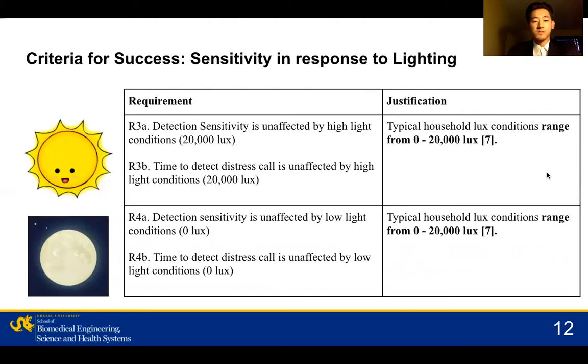The following requirements describe sensitivity performance in response to different light conditions. Lighting affects the functioning of not only the retina, but also constrictor and dilator muscles in the eye, which may affect EOG signals. For requirement 3A and 3B, detection sensitivity and time is to be maintained under high lighting, or 20,000 lux, and likewise for requirement 4A and 4B under 0 lux.